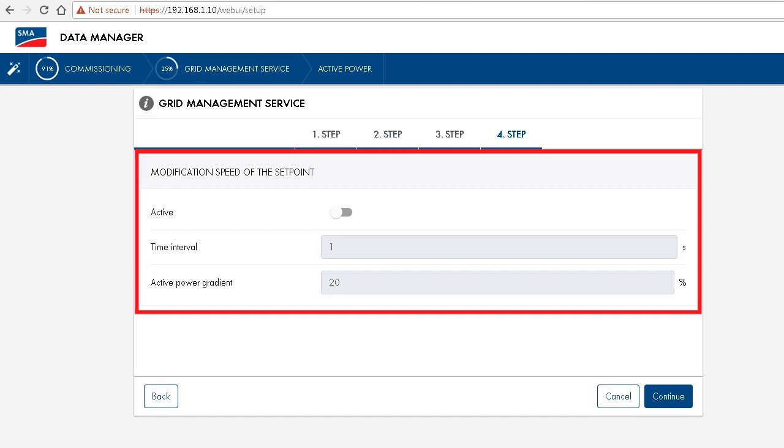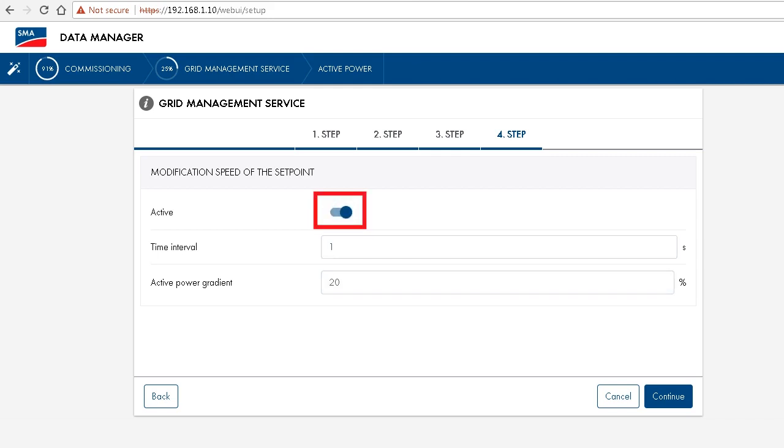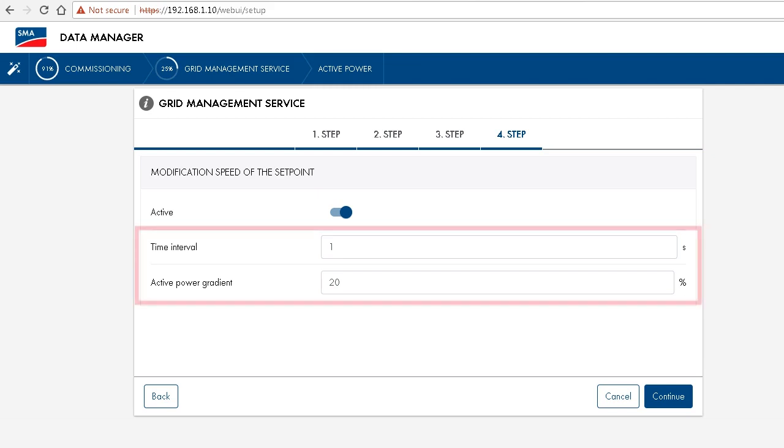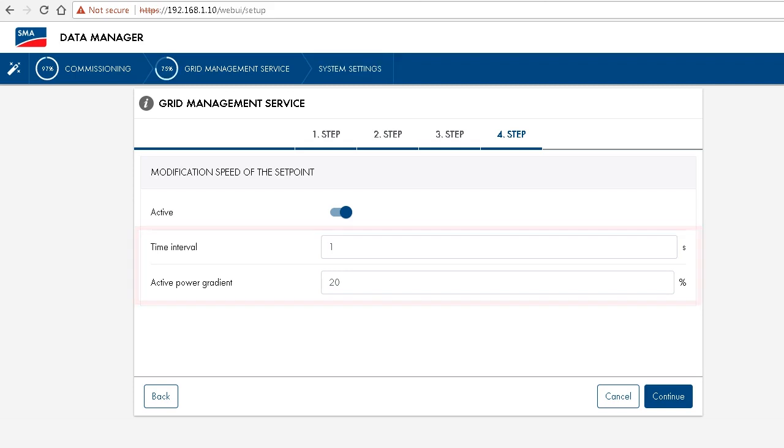At this next step, we can also define the modification speed of the set point, or in other words, the active power gradient. In order to do this, we simply choose active at this point. And then the currently configured active power gradient, in our case a maximum of 20 percent per second, would be activated.